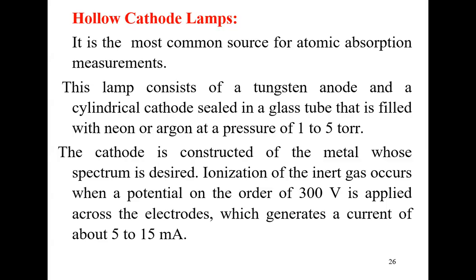Usually you will see the current on the lamp. You don't want to operate at that very high current for a newer lamp. You start at low current. If it degrades, then you increase it a little, right? And you will see what's going to happen. After it has been sputtered, you'll see some black stuff on the glass because of the bombardment of those gases on the walls of the quartz tube.